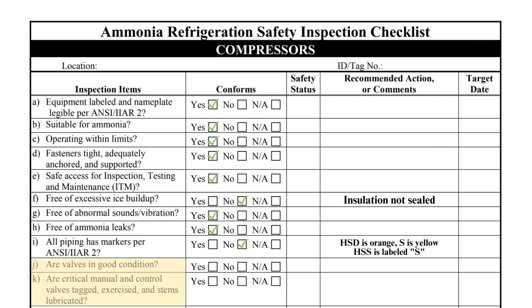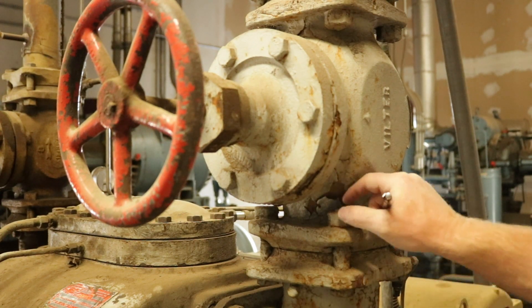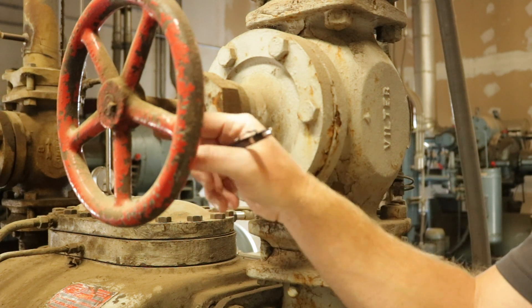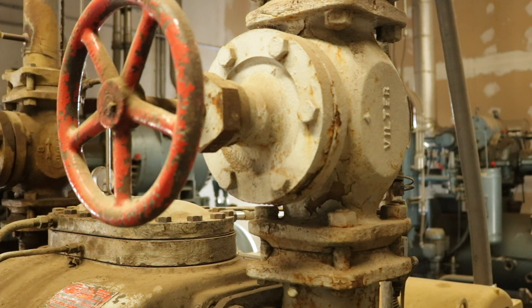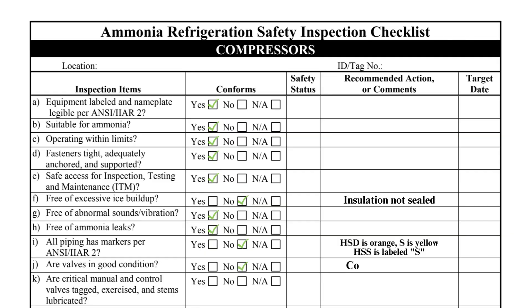Items J and K pertain to valves associated with the compressor. All valves should be visually inspected. Deficiencies that should be recorded include corroded or painted stems, missing hand wheels, damaged seal caps, or excessive valve body corrosion. This valve has moderate external corrosion and the valve stem has noticeable dirt buildup, both of which should be recorded as findings.